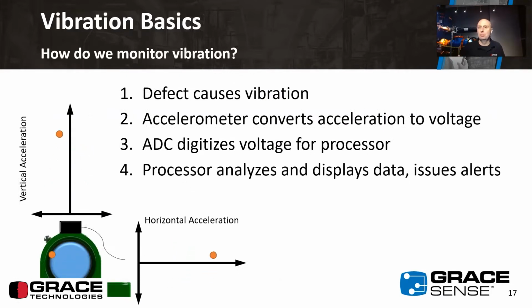Okay. So once we have this in place, how do we actually figure out that something's going wrong? Well, there are a lot of different parts to that, but the way this plays out, and I'll use this simple graphic to describe it, is you have a defect. In this case, that unbalance we talked about earlier, right? So that shaft is not spinning totally perfectly, and that's causing a vibration of that pillow block bearing. The accelerometer that we placed on top of this pillow block is going to convert that acceleration into a voltage, which we're then going to take into an analog to digital converter. That's on the sensing or processing component in the system, and that's going to make that analog signal available to the computing parts of the system. It'll then be analyzed and used to either display in a graphical form or to issue an alert to your maintenance team. Whatever. This is the very, very high level view of how this works.